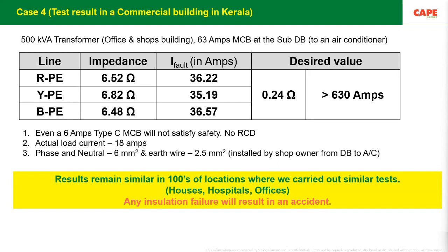And then we got in touch with the designer of that particular building. Interestingly, he told that, no, this cannot happen in my building because I designed the building based on the IS 3043. And then when we asked, okay, did you hear of fault loop or fault loop impedance? He told, yes, I did as per IS 3043, but he never heard the name fault loop impedance. And this name is written in the standard in IS 3043. 66 places this name, its definitions, its application are written. In IS 732, about 62 places fault loop impedance and disconnection times and disconnection methods are explained. But this is unknown to the user. Of course, he is not an electrical engineer, but unknown to the contractor, unknown to the designer. This is the pathetic situation.